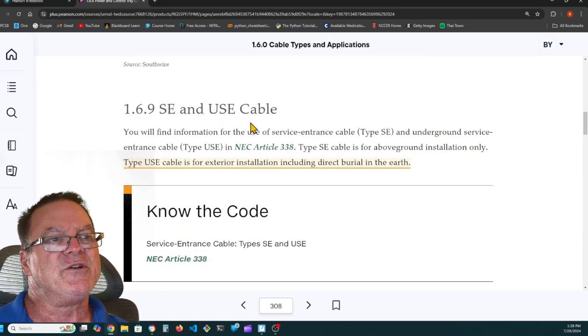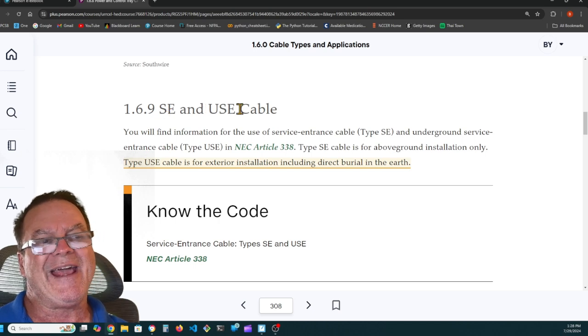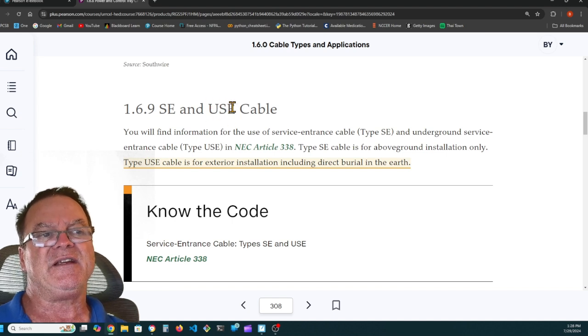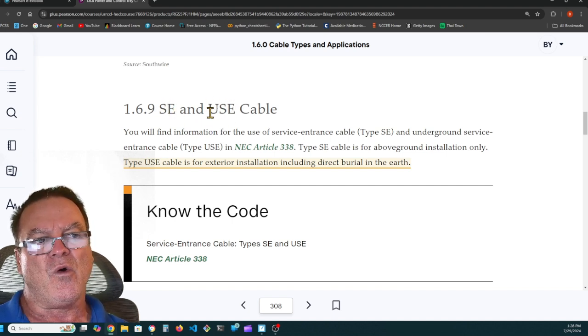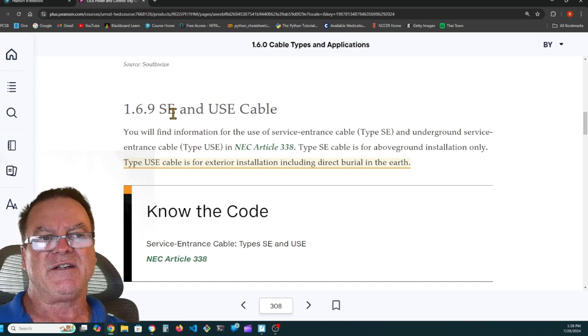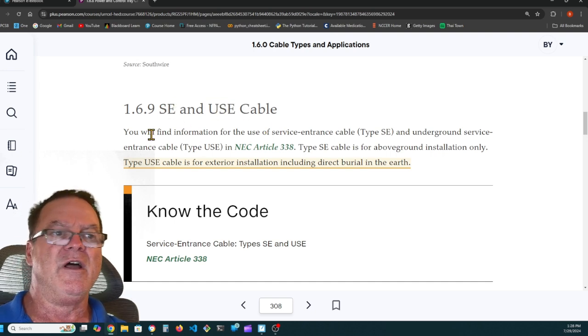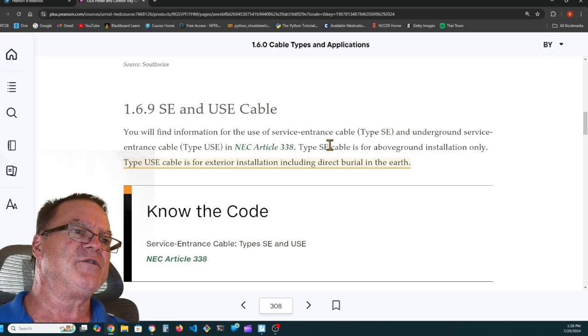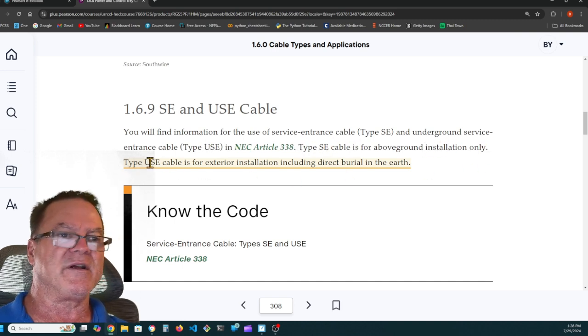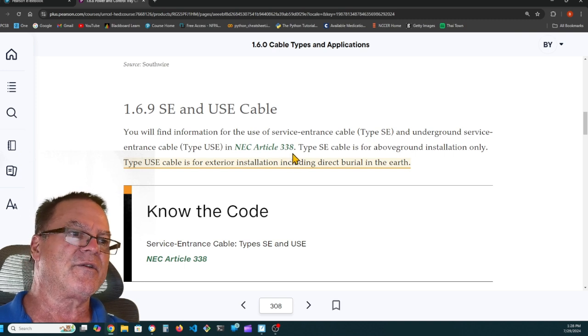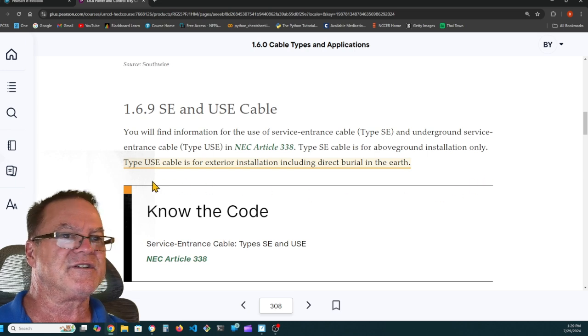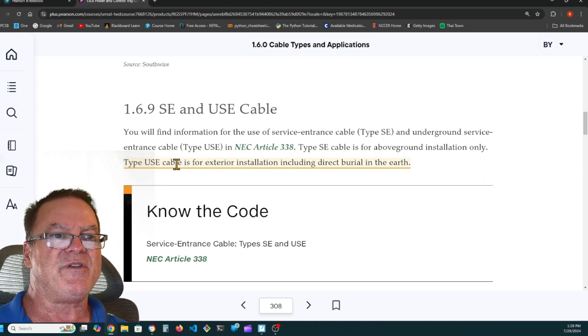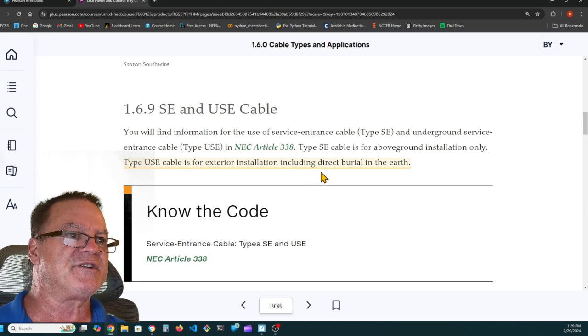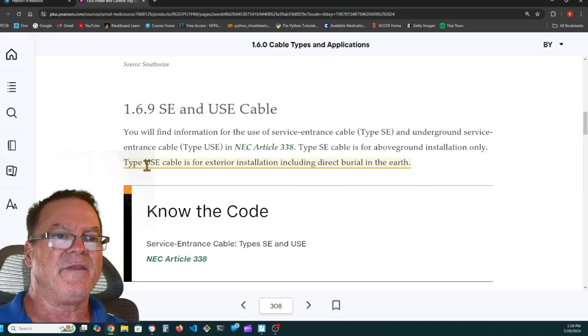1.6.9 SE and USE. This is not "use" cable. You don't pronounce it "use." It's underground service entrance, USE. So call it service entrance or underground service entrance. It's type SE or type USE cable. You'll find information for the use of service entrance cable and underground service entrance cable in NEC Article 338. Type SE cable is for above ground installations only. This is highlighted. It says type USE cable is for exterior installation, including direct burial in the earth.